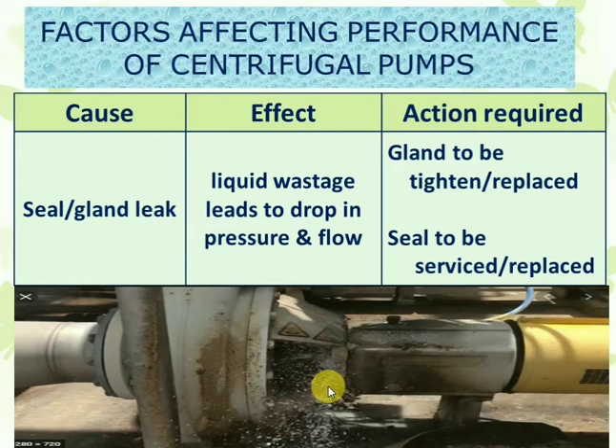So what should we do? In the case of gland packing, we should tighten it or replace the gland packing. In the case of seals, we should stop the pump, isolate it, go for maintenance, replace the seal or service the seal, and completely arrest the leak.